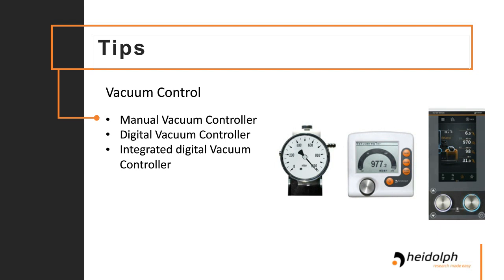Lastly, and usually the most effective, is an integrated digital vacuum system, usually with your rotary evaporator all built in. This will make use of a valve and will allow you to accurately control your vacuum through your panel. Yes, and there are also very modern systems that can control an RPM-regulated pump directly.